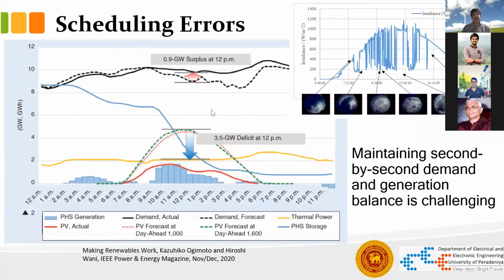This reserve is so many megawatts of spinning machines which are not generating any power. There are also prediction errors. Even if you can predict the solar PV properly, here in Japan they were predicting that much solar, but solar didn't come that much. There was a deficit of 3.5 gigawatts because of the prediction error. Also, they were predicting the load like that, but load didn't come all the way, it had a surplus. The dotted line is the predicted load, and the black line is the real load.